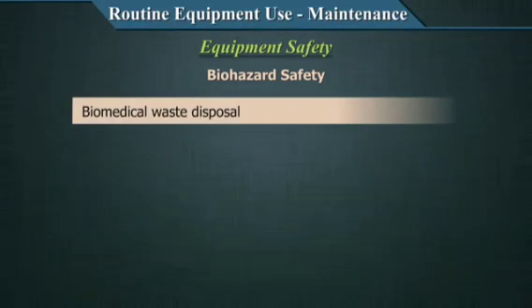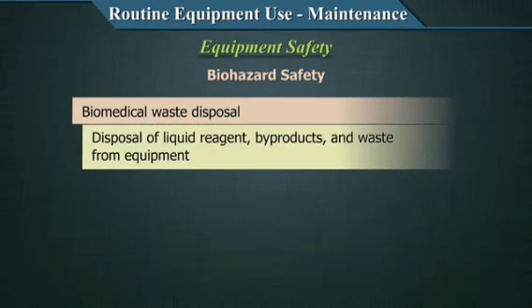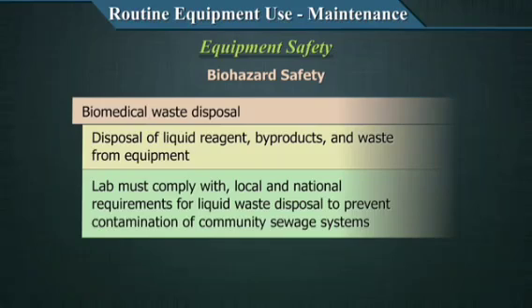From decontamination, we move on to biomedical waste disposal. Most equipment will generate liquid waste, both reagent waste, byproducts, and waste from the samples. All these will become part of your equipment effluent. Effluent is a major concern for laboratories. When placing equipment in the laboratory, it should be made sure how liquid waste will be handled. Be aware of this and comply with local and national requirements for liquid waste disposal in order to prevent contamination of the community sewage systems with pathogens and toxic chemicals. So management of liquid effluents is a very important thing that we have to think through while we are operating our equipment in the lab.